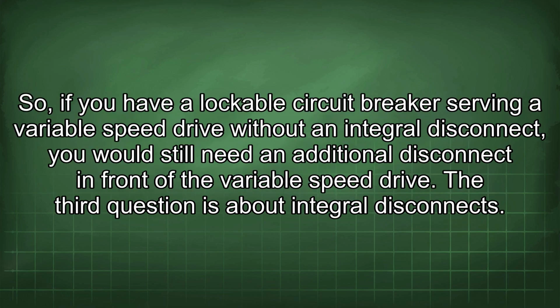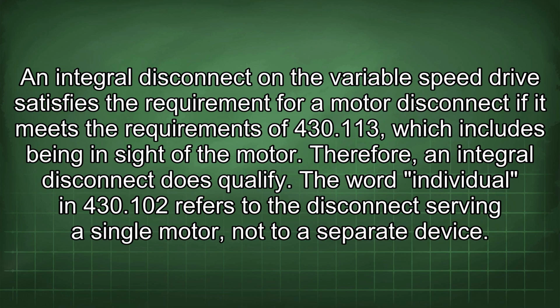So, if you have a lockable circuit breaker serving a variable speed drive without an integral disconnect, you would still need an additional disconnect in front of the variable speed drive. The third question is about integral disconnects. An integral disconnect on the variable speed drive satisfies the requirement for a motor disconnect if it meets the requirements of 430.113, which includes being in sight of the motor. Therefore, an integral disconnect does qualify. The word individual in 430.102 refers to the disconnect serving a single motor, not to a separate device.